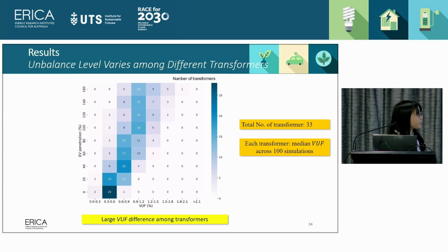0.6%. And with the increase of the EV penetration level, the voltage unbalance factors of each transformer keep increasing. At 160%, there are 13 transformers in a relatively large range, that is 0.9 to 1.2%. And more importantly, I want to point out that there are large voltage unbalance differences amongst different transformers. So still looking at the EV penetration level of 160%, there are 13 transformers in the range of 0.9 to 1.2%, and there are 5 transformers in a much larger range, that is 1.5 to 1.8.